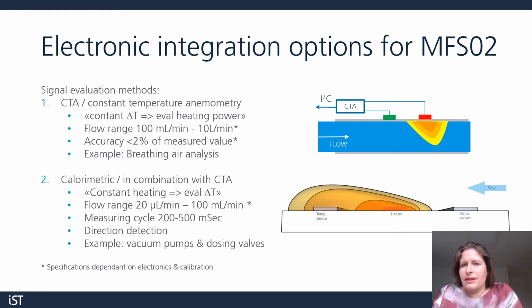With classic constant temperature anemometry, as you can see in the top picture, we can use the sensor to cover a dynamically changing flow rate. To stick to air analysis, we can evaluate a child's or an adult's breathing with less than 2% accuracy, by evaluating the heating power required to maintain a constant over-temperature on the microheater.